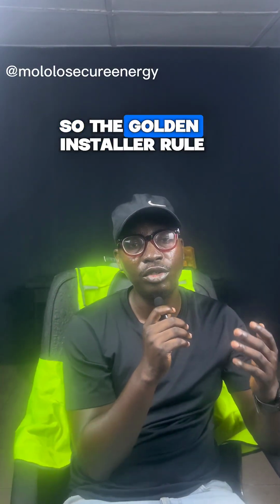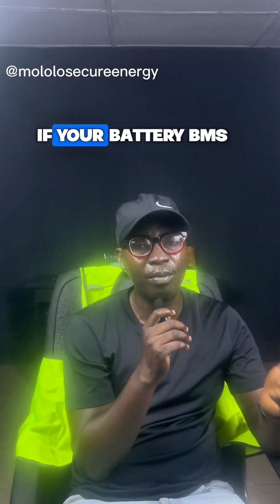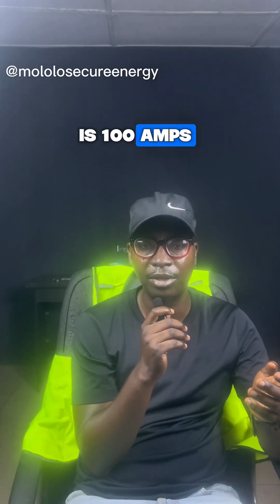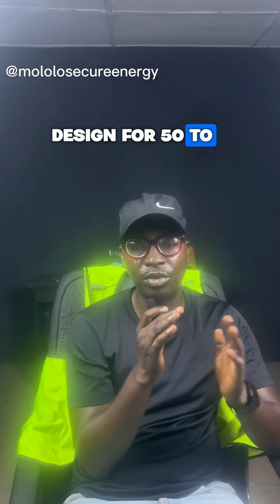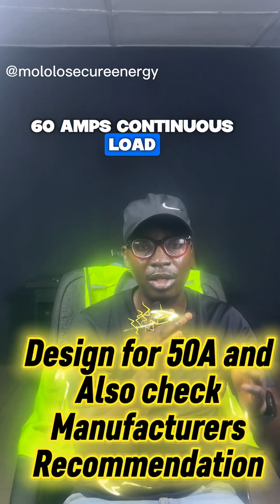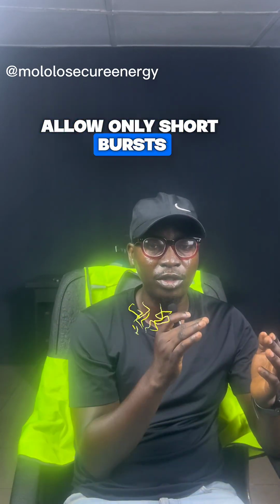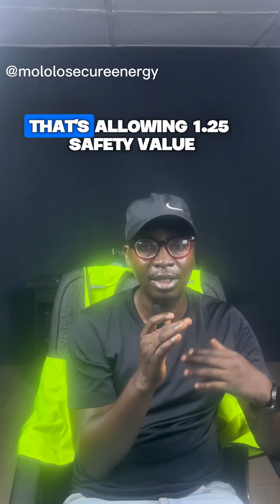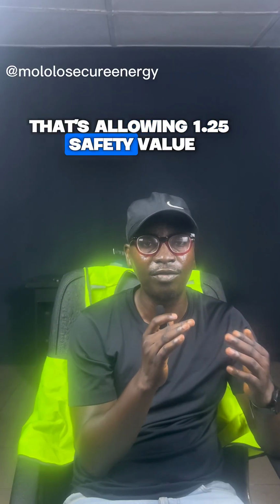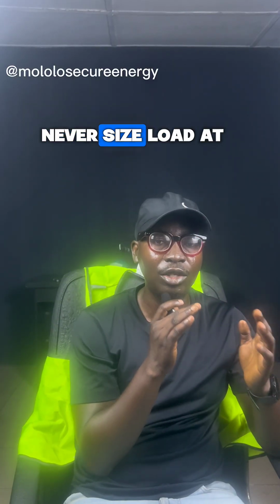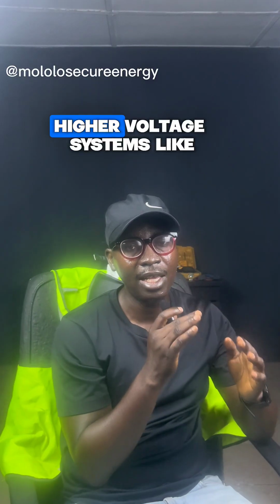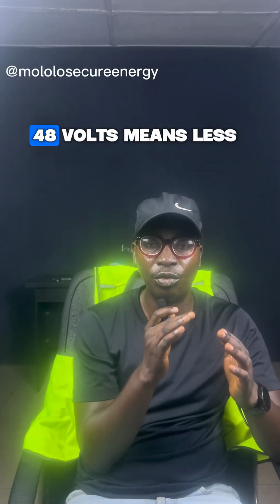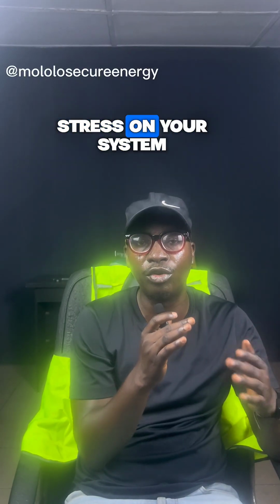So the golden installer rule, if your battery BMS is 100 amps, design for 50 to 60 amps continuous load. Allow only short bursts up to 80 amps. That's allowing the 1.25 safety value. Never size load at full rating. Higher voltage systems like 48 volts mean less stress on your system.